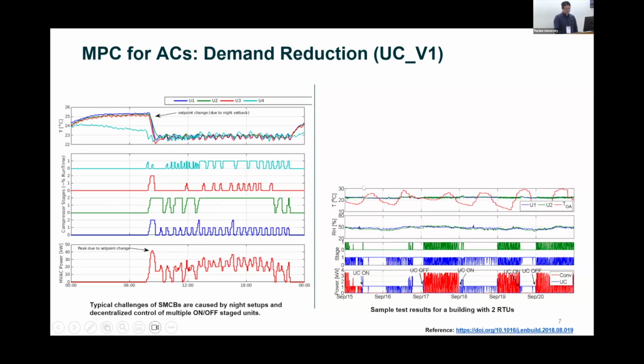So this is the example result once we developed the model predictive control that coordinates the peak demand for the 2 units in this case. Again, temperature, relative humidity, each stage of the compressors, and the total power. And the red one is the typical control. The set point in this case is fixed for several days, about a week. And randomly, we switched the model predictive control unit coordination on, and switched it off, which goes back to the decentralized thermostat controls. We kept repeating this, and you can immediately see that the model predictive control unit coordinator is regulating the peak. It is not allowing all the units to be activated at the same time, very clearly in here.